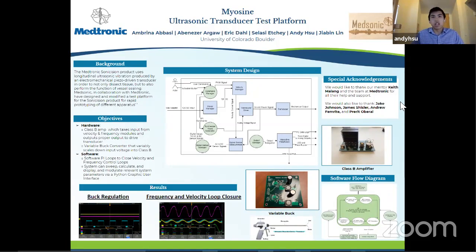But like Eric said, due to our hardware constraints and due to specifications by Medsonic, we decided to use the two processors that are currently on board. And that is the main C28X core, which is made by TI, and a coprocessor called the CLA that sits right next to it.